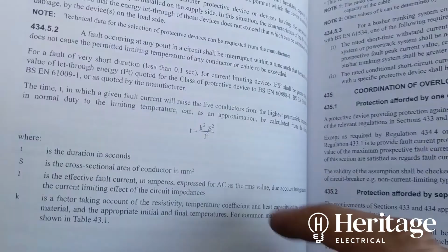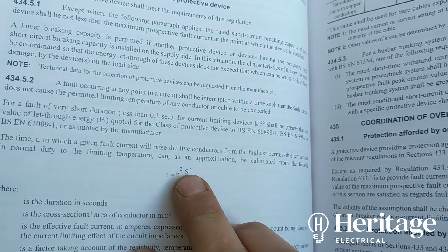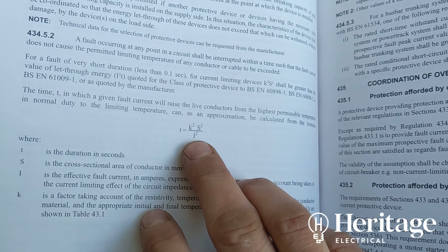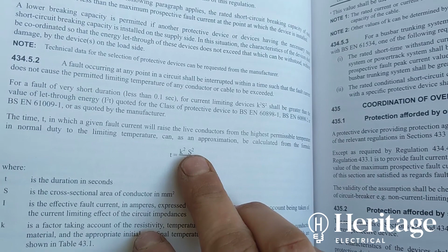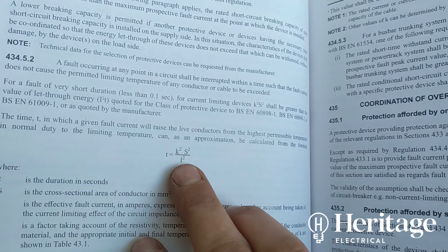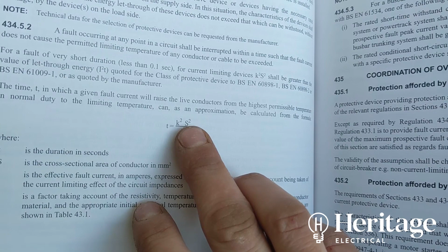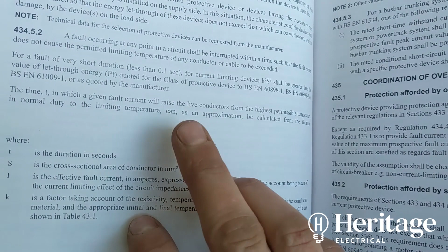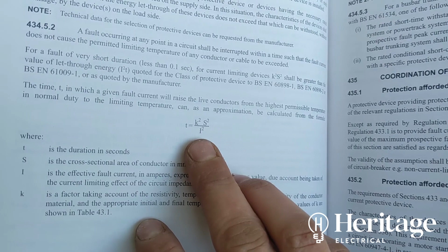So we then plug that into the adiabatic equation. So we've got time, we've got a constant depending on what type of cable we use, we've got the cross-sectional area of the cable, and then we've got the fault current. So if we rearrange that, then we can ascertain that if it takes 3 seconds to trip, fault current's a certain value, that's a constant, it will then throw us out a cable size required to carry that fault current for the duration needed before that fuse fuses. And in this case 16mm tails are more than adequate to carry the fault current for the amount of time required for that fuse to trip if there is a fault. So I'm happy with using 16mm tails. So it's just a bit of an afterthought.